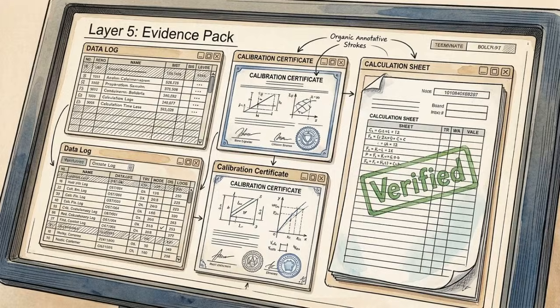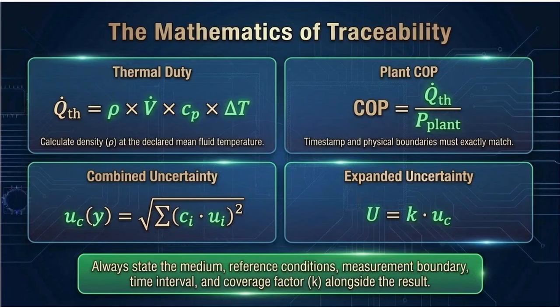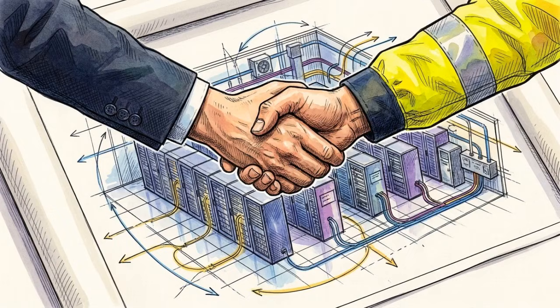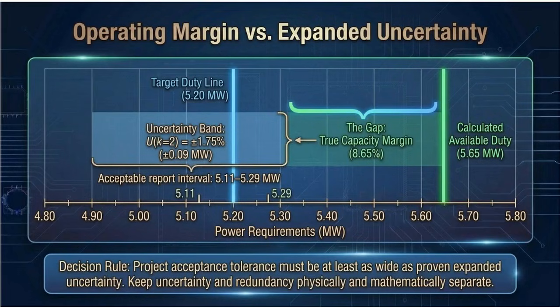This slide details the mathematics of traceability. The top panels display core formulas for thermal duty and plant COP, whose variables must match exact boundaries. The lower panels outline uncertainty calculations, determining the total margin of error for the entire measurement system. This mathematical uncertainty dictates the ultimate decision rule for contractual project acceptance. This graph plots operating margin against expanded uncertainty. A facility cannot claim an operating capacity if it falls within its measurement system's margin of error. The true capacity margin must demonstrably clear this expanded uncertainty band.